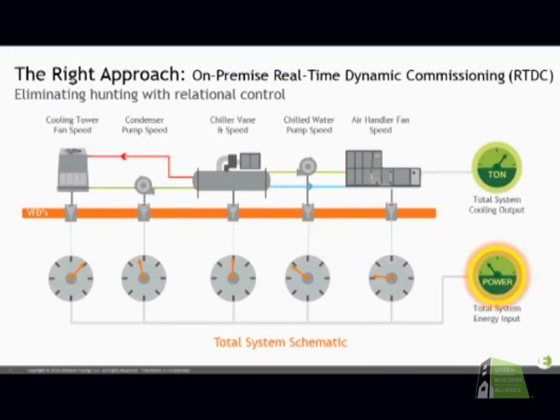So typical design scenario for this type of plant, you'd have maybe a 90% set point, or maybe you're maintaining a given static pressure for that pump and a given temperature discharge from the cooling tower, and you're just maintaining these individual set points. What you really want to be looking at is how the system is operating together. And probably the easiest way to think about this, I'm an engineer, so I get into the weeds, so feel free to ask questions if I get too into it.